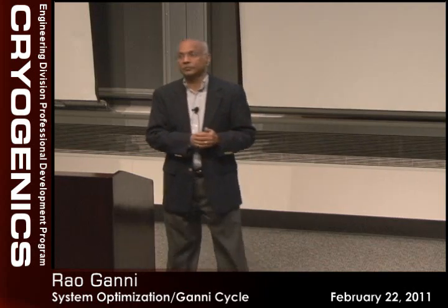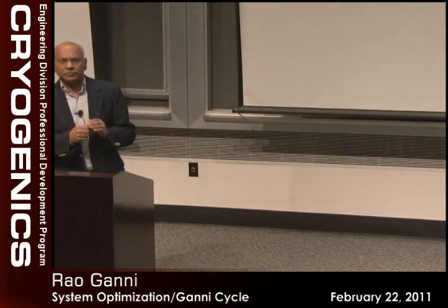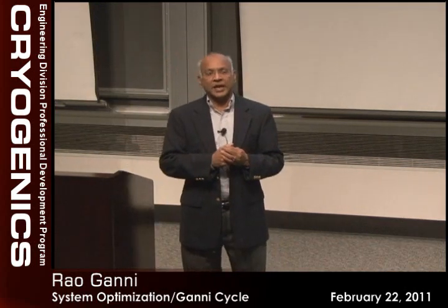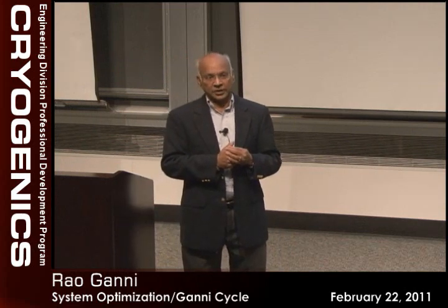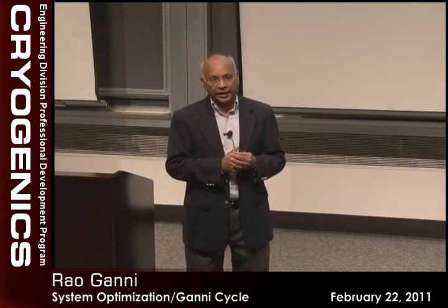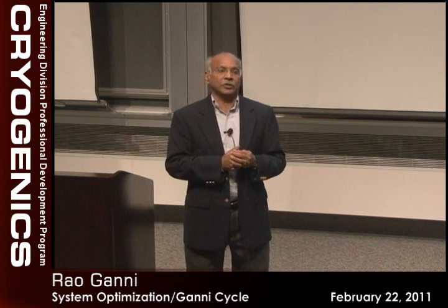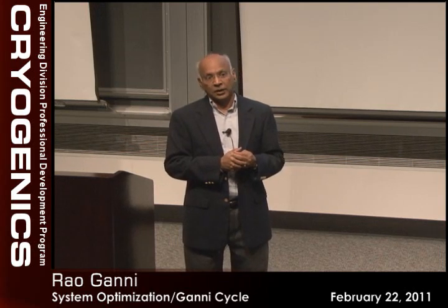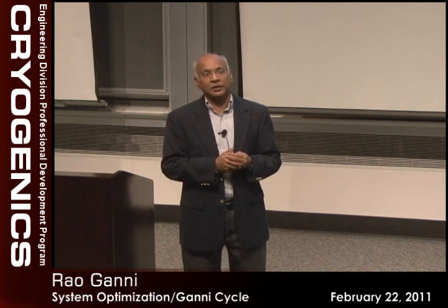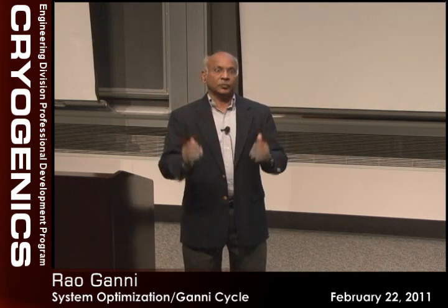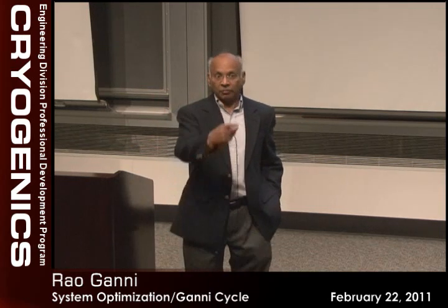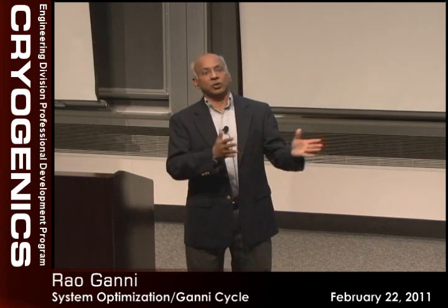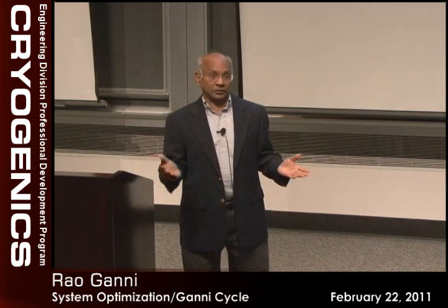Anybody else? Yeah, Robert. You talked a lot about power savings. What about liquid nitrogen consumption? Liquid nitrogen consumption is directly proportional to the heat exchanger size, HX1 going from 300 to 80 K, and that trade-off is how much capital you want to invest versus how much nitrogen. That's how we look at it to see what is the optimum when we optimize the nitrogen. We'll address that next week. I'll show you where you come up with the turbines to replace that altogether. That's the next class.